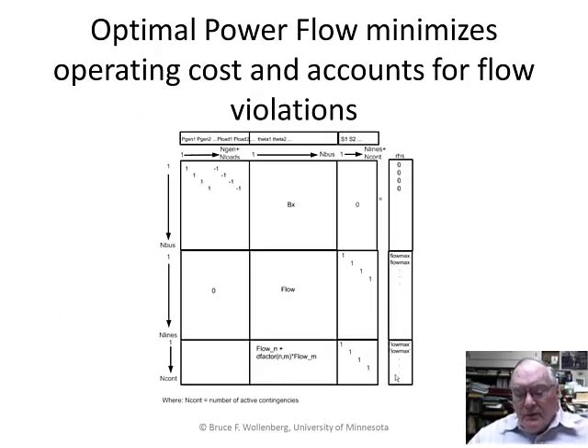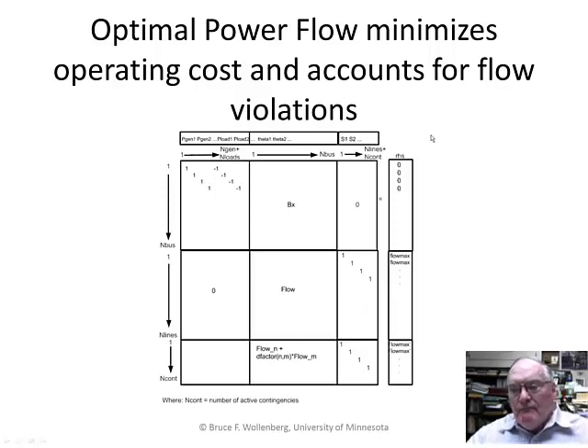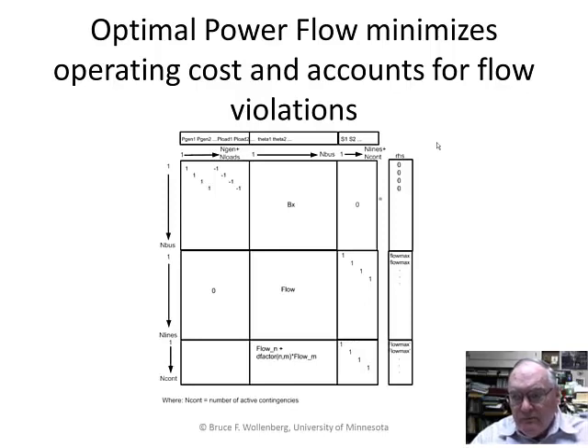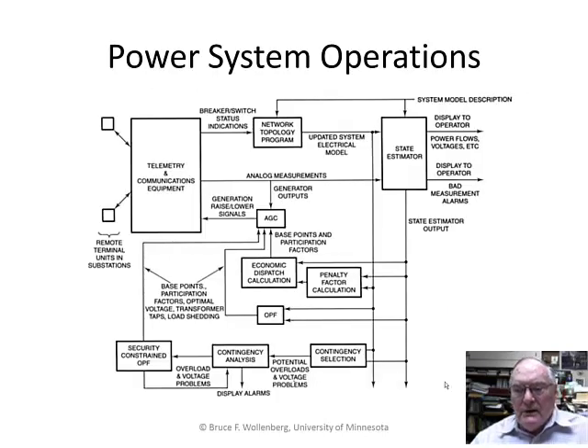Violations must be corrected — usually by changing the pattern of generation, going off of pure economic dispatch — and must be corrected in real time, as fast as possible. The economic dispatch must also account for transmission losses; for electrical engineers, these are the I-squared-R losses that cause lines to heat up. We can't eliminate all losses, but we can minimize their economic effect. This leads to the optimal power flow, and we cover in the text how to build an optimal power flow that models the power system, accounts for all flows in the network so that none of them overload, and includes constraints representing first contingency flows — called a security constrained optimal power flow.